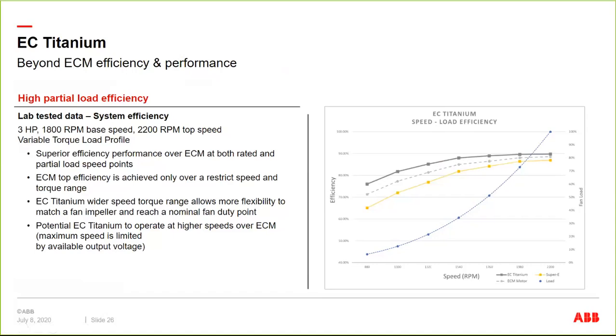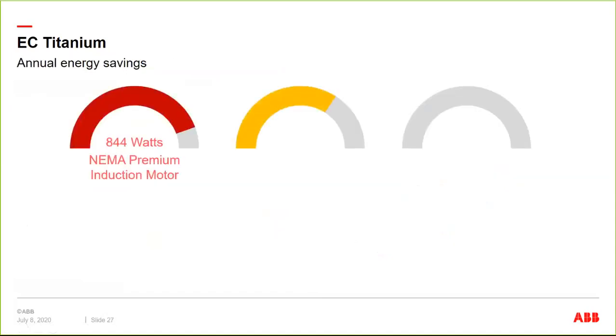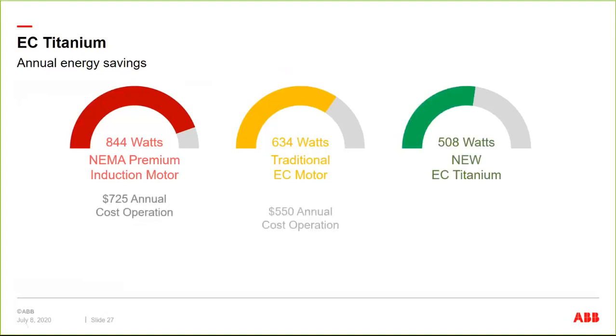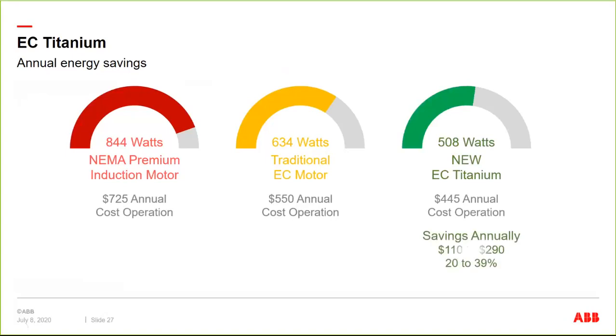So how does that really translate to energy savings? So we basically took that lab test data. So that wasn't just a made-up curve. That was actual lab test data that was just put into a curve. And then we ran those calculations over that bell-shaped operational curve at those load points and the different efficiencies. And then when you do your payback, you can actually see like an induction motor would cost over $725 annually to run that 3 horsepower motor. And we're saying, since we're maintaining our efficiencies higher at those partial load and speed points, it's only $445. So that can be up to a 20 to 40% energy savings over traditional designs, and really help as far as the payback analysis when selling new equipment to customers that are looking for energy savings.